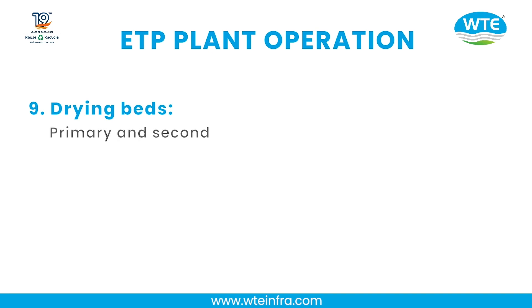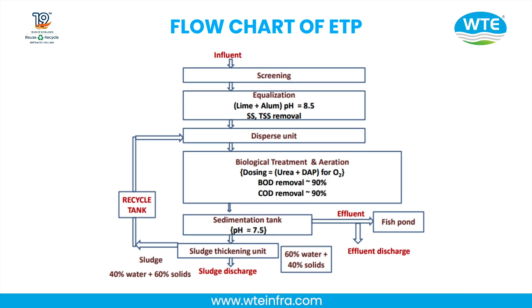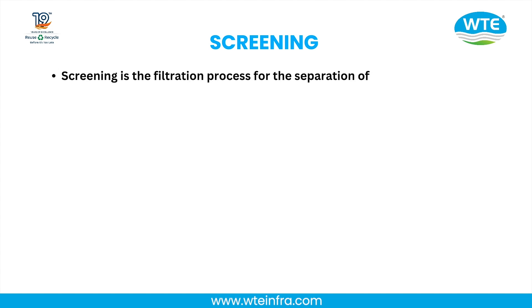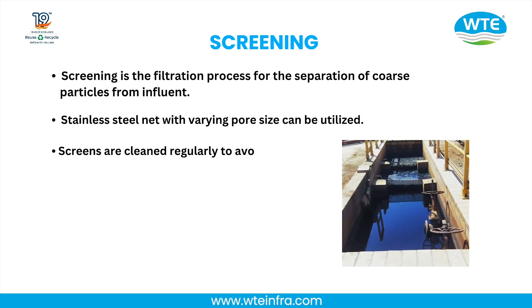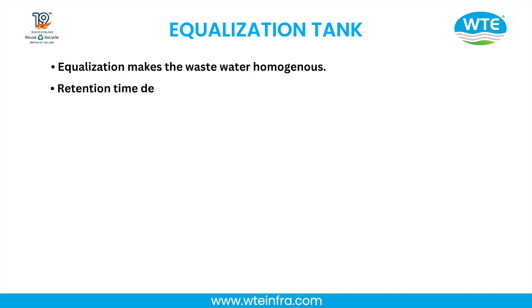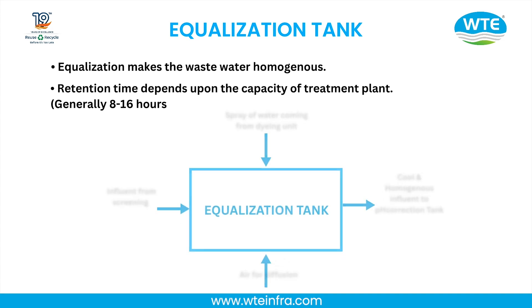Step 9 — Drying Beds: Primary and secondary sludge is dried on the drying beds. Screening is the filtration process for separation of coarse particles from the influent. Stainless steel nets with varying pore sizes can be utilized. Screens are cleaned regularly to avoid clogging. The Equalization Tank makes the wastewater homogeneous; retention time depends upon the capacity of the treatment plant — generally 8–16 hours.